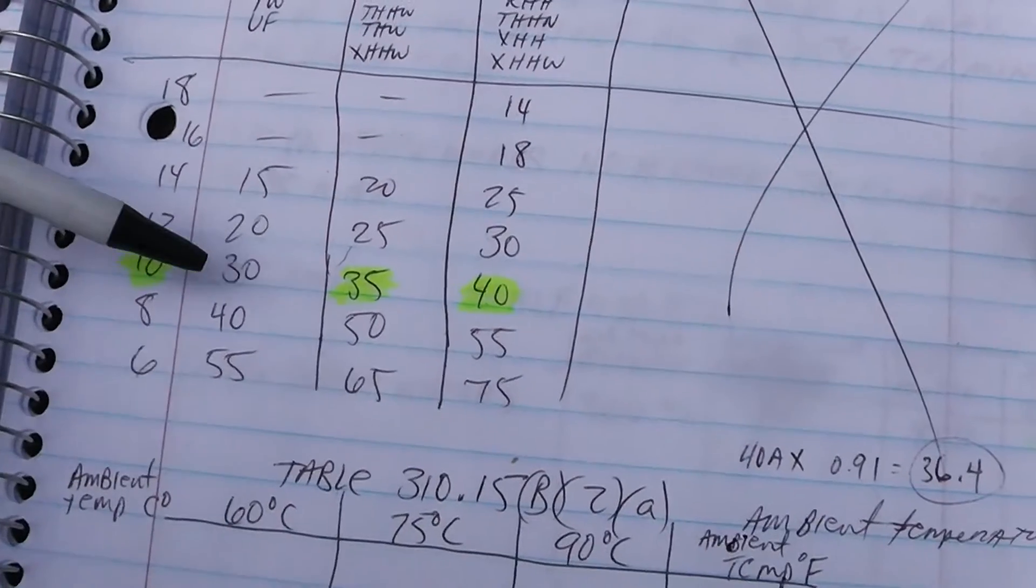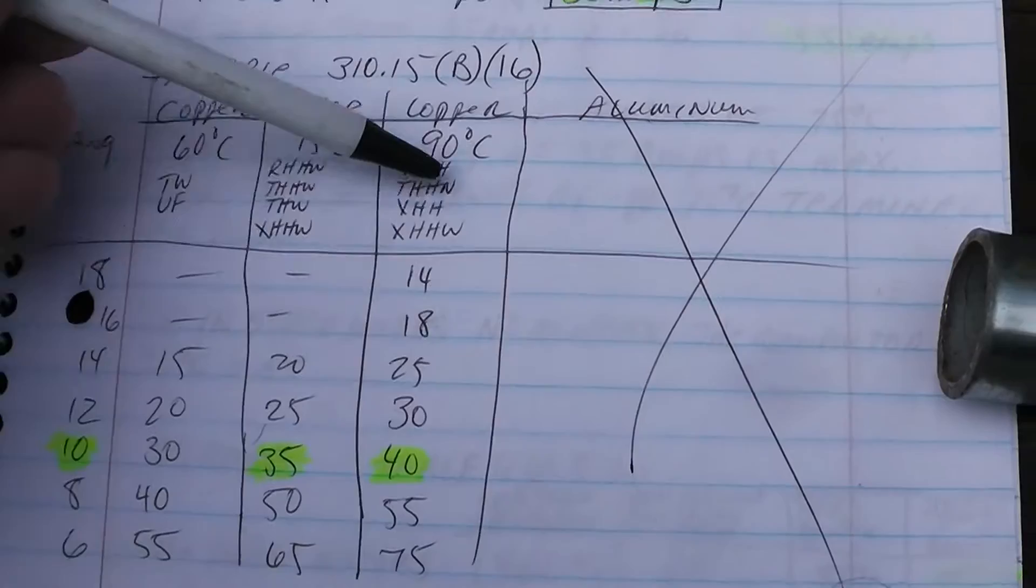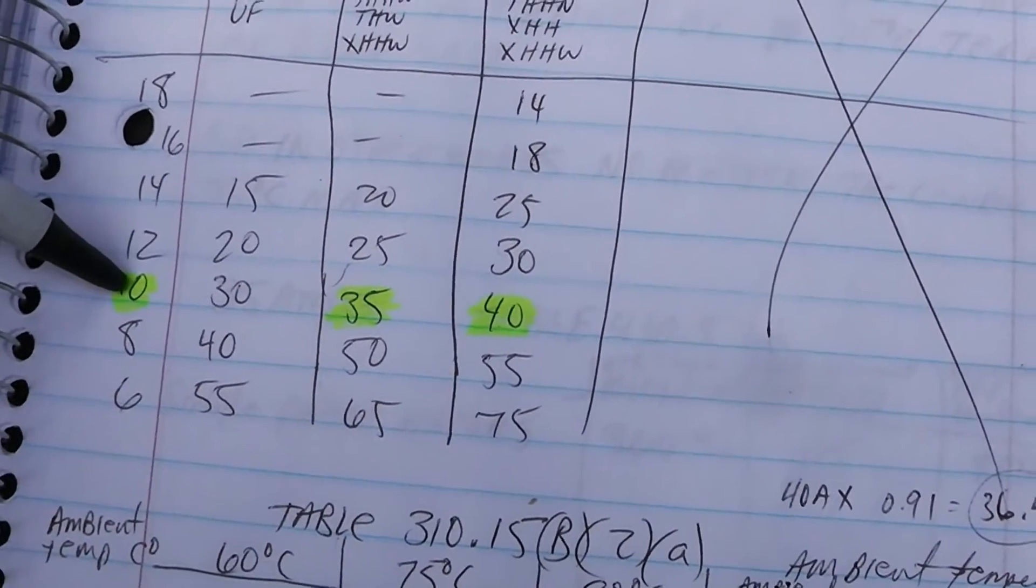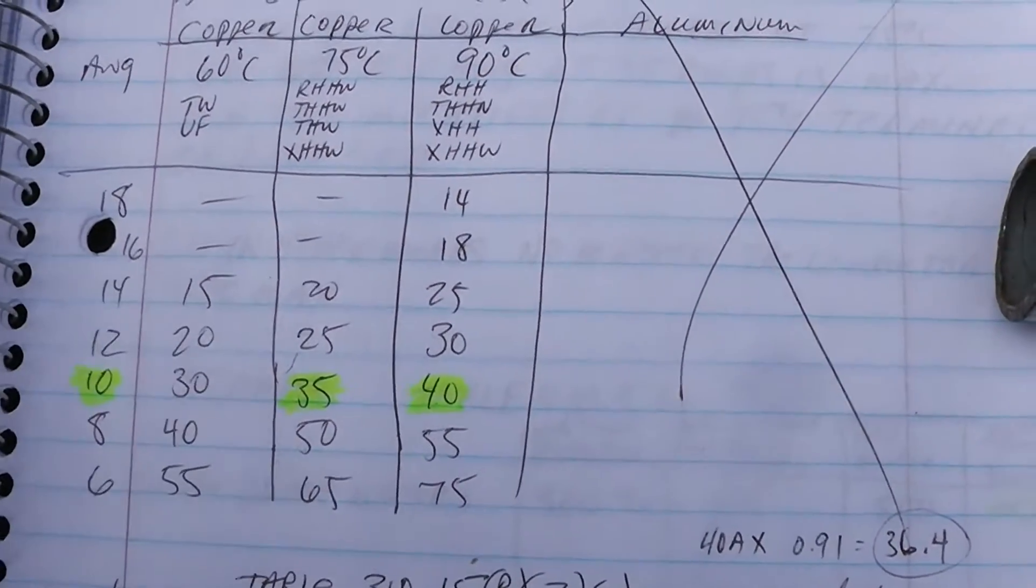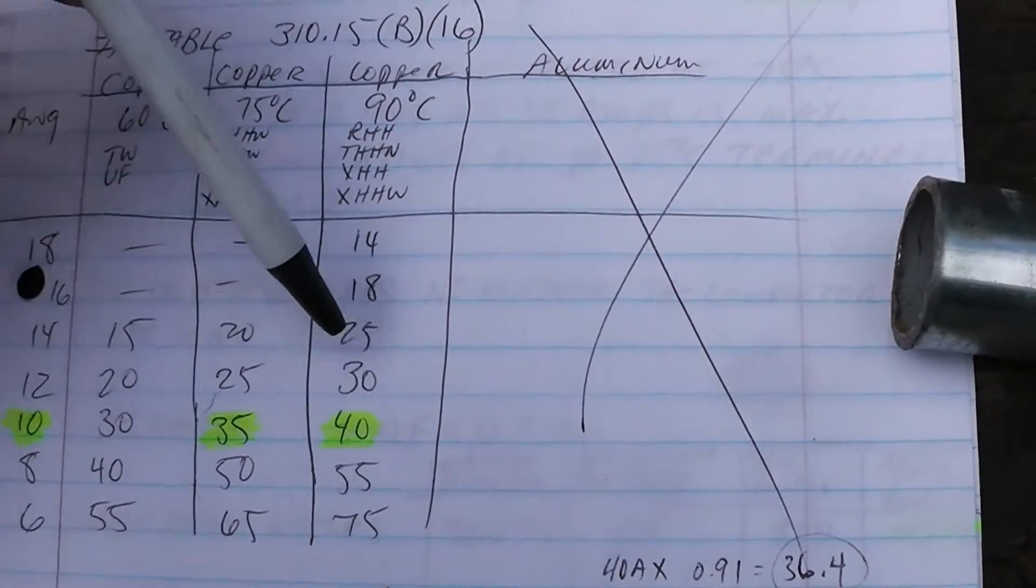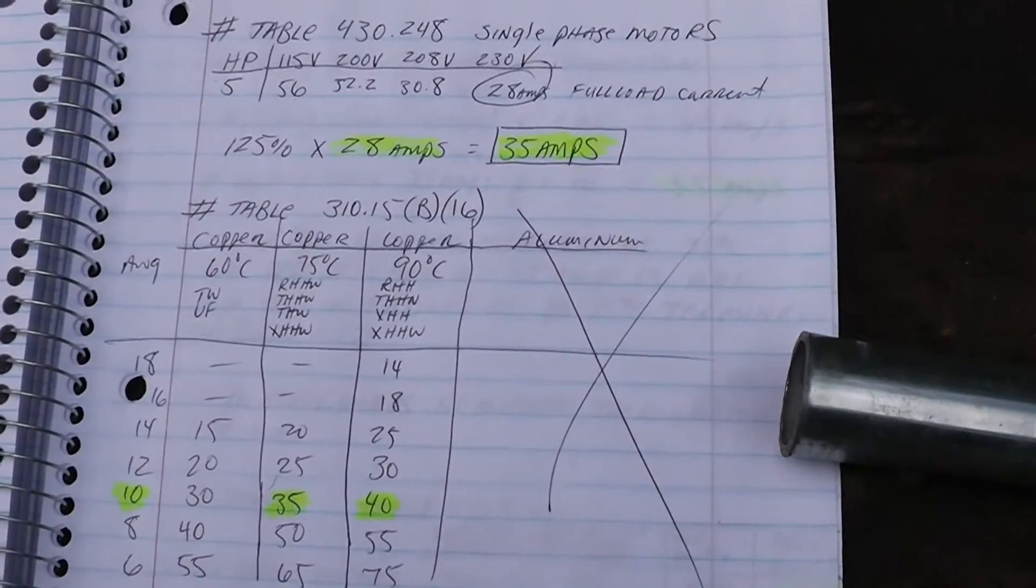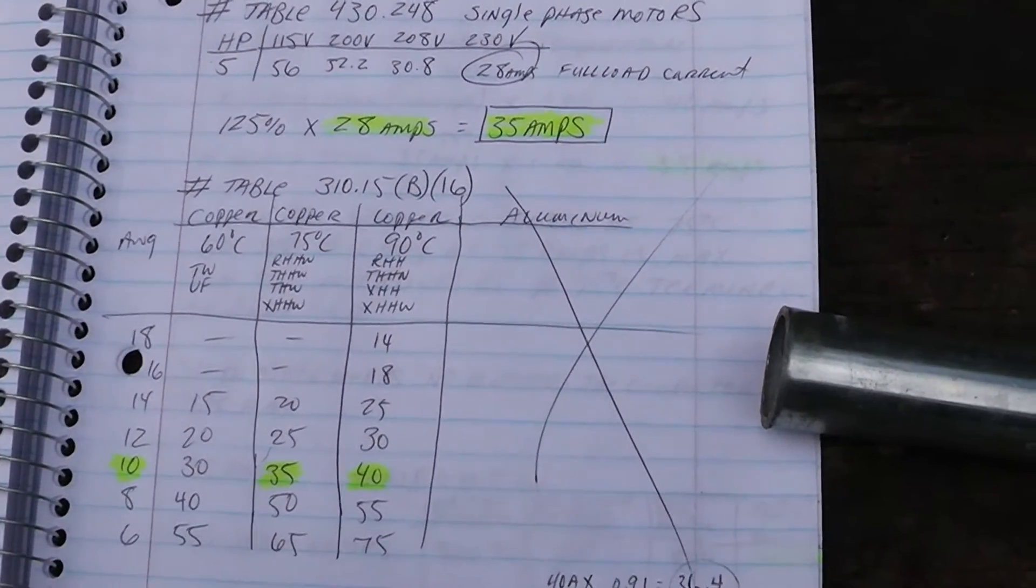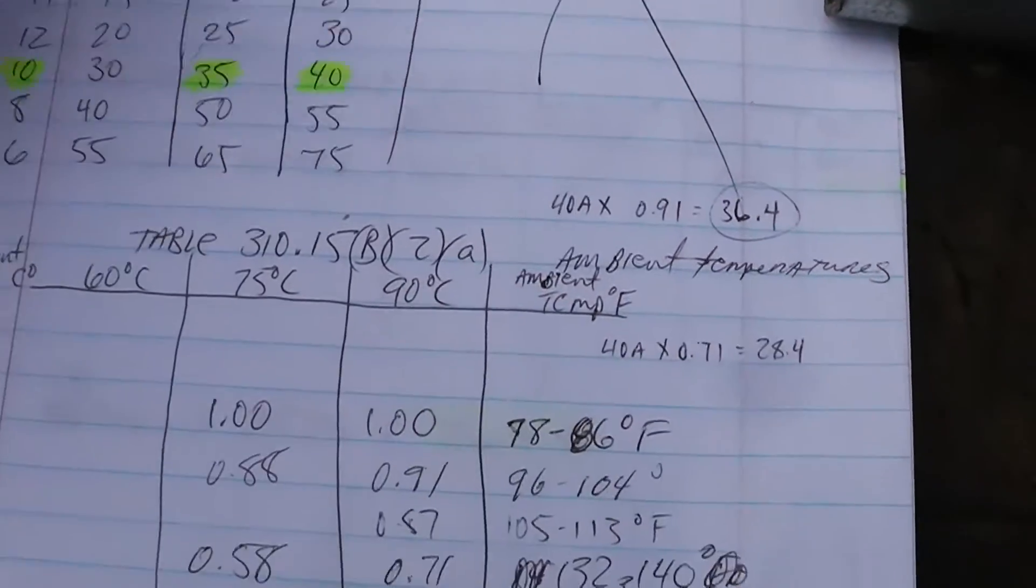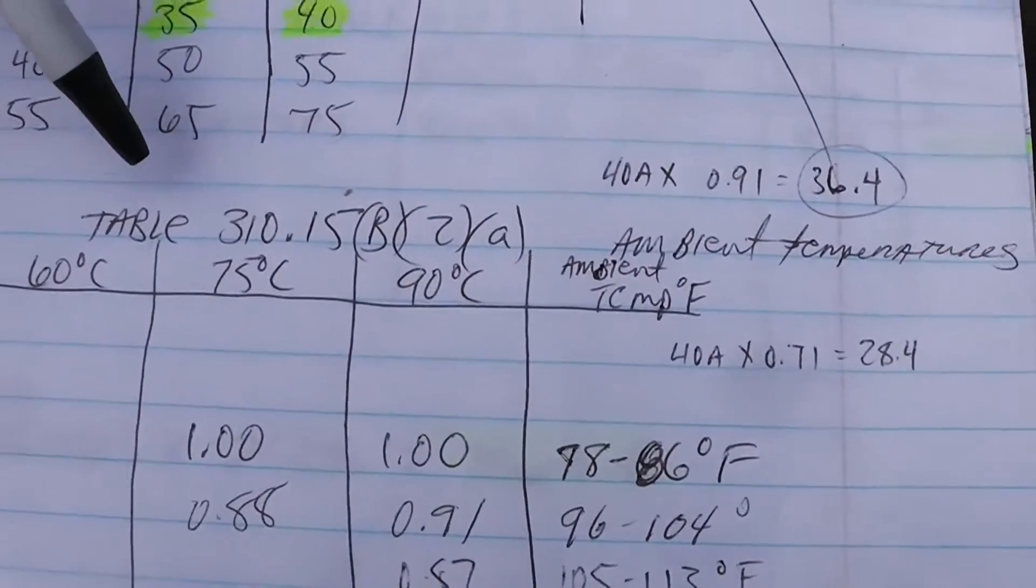I'm going to be using THHN, which gives me the highest insulation value. We need 35 amps and we can use number 10. You want to go number 8 or number 6? That's fine, knock yourselves out, but I'm doing the minimum requirements. I know a lot of people who jerk Romex are going to have a problem and say you can't put 40 amps on number 10 wire, and that is true in a residential situation with Romex. I'm not dealing with that.